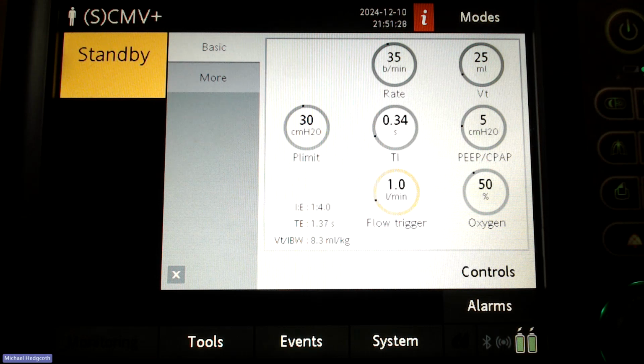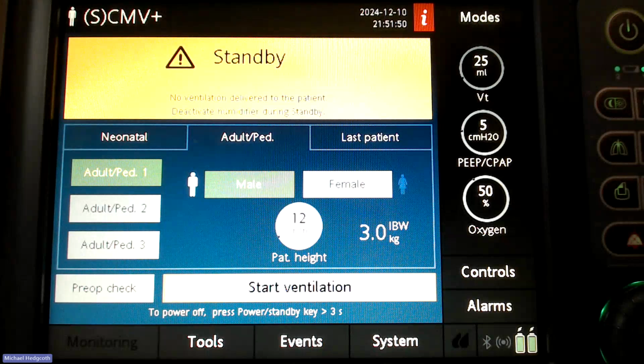From that point on, it's going to function just like it does at any other time. It's just making sure we've switched to the neonatal circuit, still using the adult ped expiratory valve and the adult ped flow sensor with the neonatal circuit in between, and then compensating for that added dead space in the larger flow sensor.